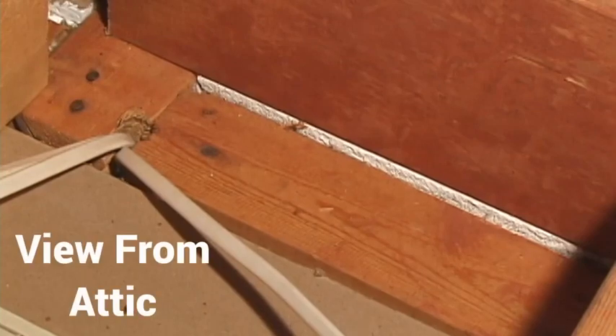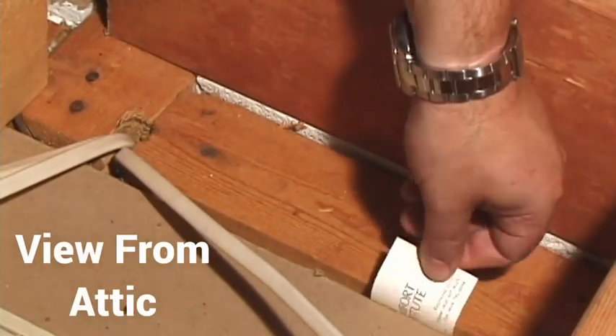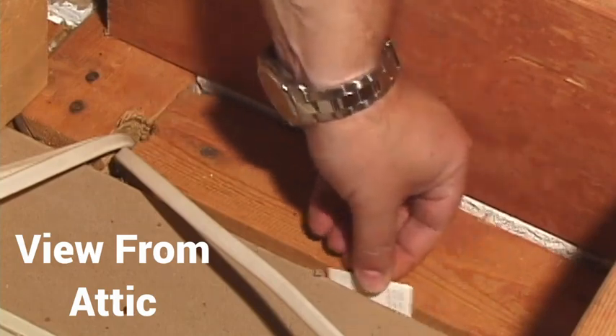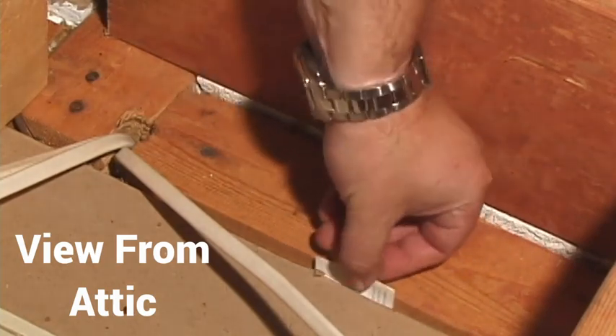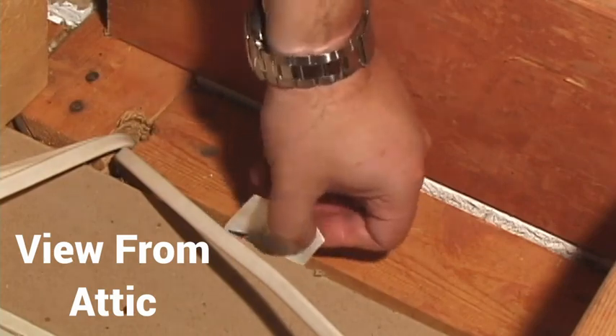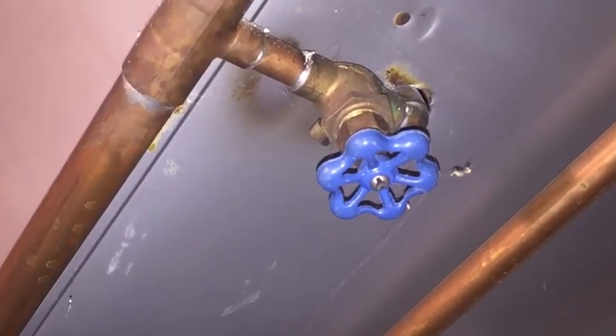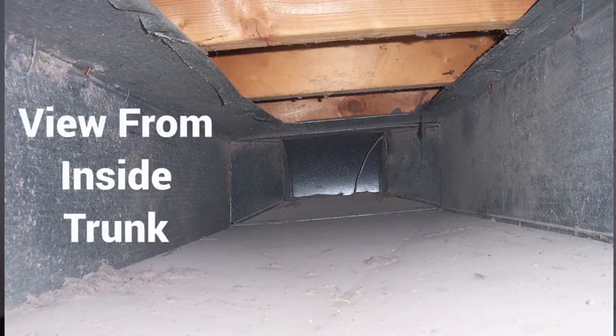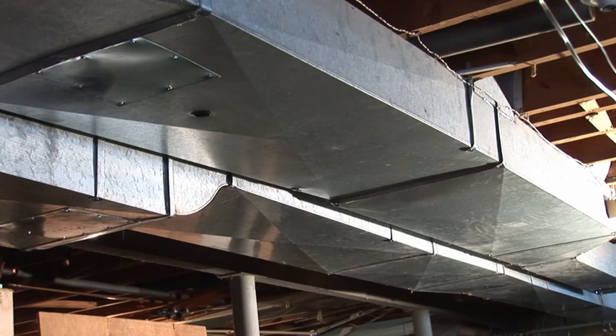Because of the many return inlets, the return side of these systems is usually quite extensive. Combined with the way that they're put together, the result is always a ton of what I call smallish leaks. Every running foot of the drywall to vertical wood studs, and the horizontal top plates leaks a bit. Holes for the electrical wiring are routinely drilled through the wood studs and joists, up, down, and sideways. There are larger but still aerosealable gaps around plumbing pipes or even supply ducts that pass through the wood or the end caps or panning. There are big gaps where the sheet metal trunks and panning connect to the joist cavities. And then there's lots of aerosealable gaps and seams in the metal ductwork in the basement itself.